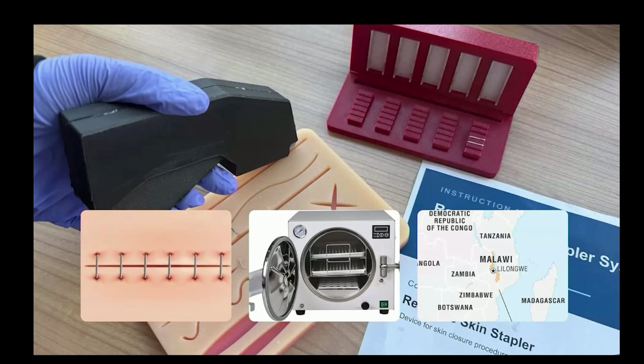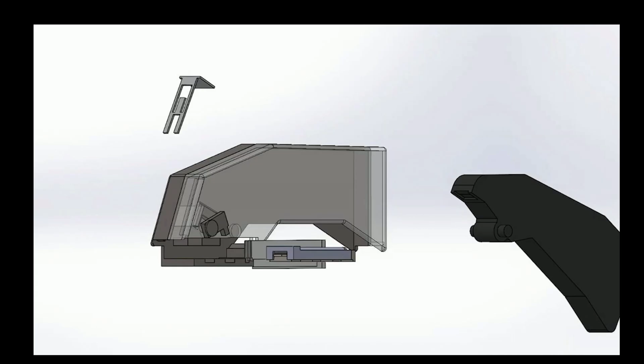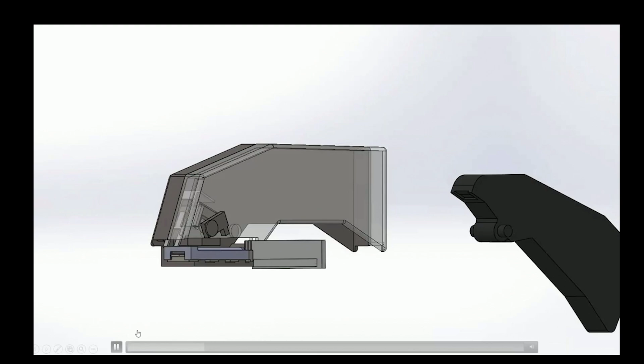Clinically, the device must safely and effectively close wounds. Mechanically, it must withstand multiple sterilization cycles. And to ensure accessibility, all parts are designed for local fabrication and long-term reuse. With components such as a reloadable cartridge that locks into place, simple internal mechanisms that allow for repair if damaged, and a fully sterilizable device, this design supports safer use across multiple procedures while reducing cost, waste, and dependence on any single-use medical supplies.